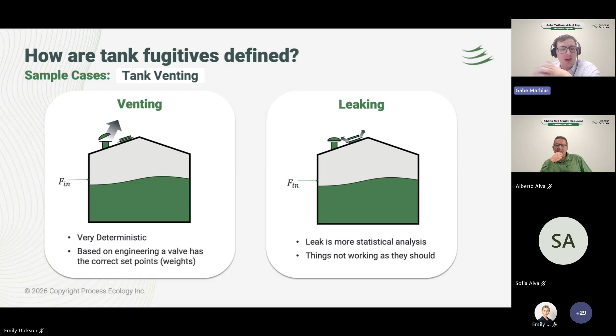And what we've done in the tool is we calculated something called the probability of leak, taking into account the theoretical versus actual, kind of what we see. And in the next slide, you see that this probability of leak is calculated with time. And in here, we have 3 tanks: the water tank, the condensate tank, and the slop tank. And we see that the water tank is definitely leaking for a long period of time during this month. And the slop tank was leaking, and then it suddenly stopped leaking after some time.